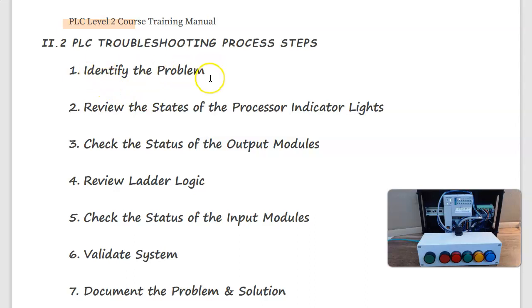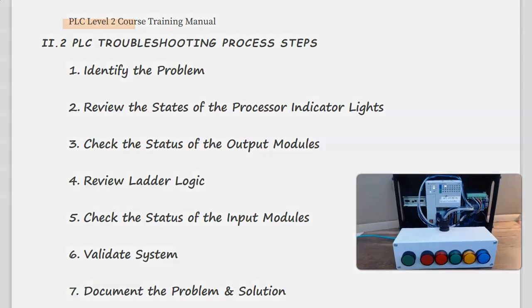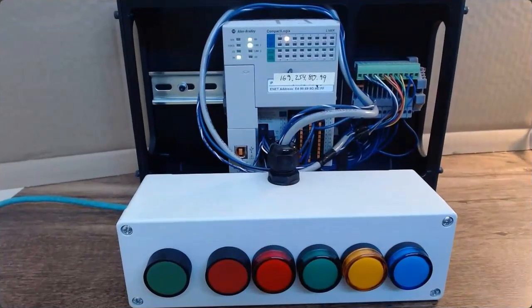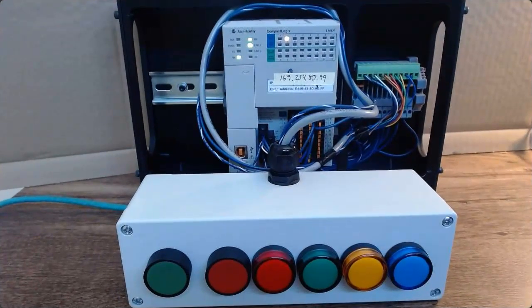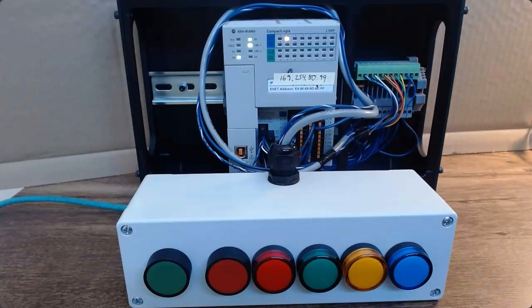We identified the problem with the operator—the IO was not responding. We then reviewed the states of the processor indicator lights and we found that the PLC was not in run mode and we were getting a fault.